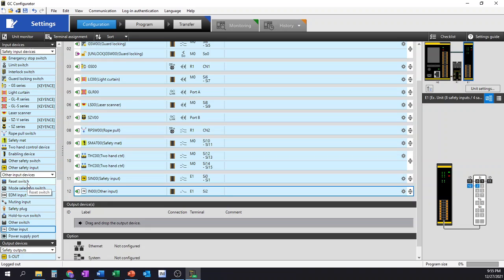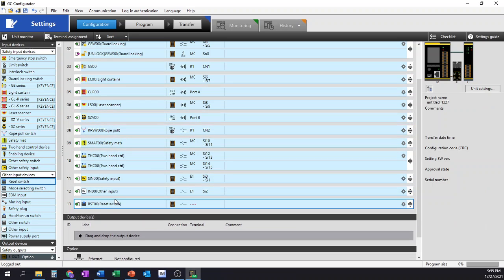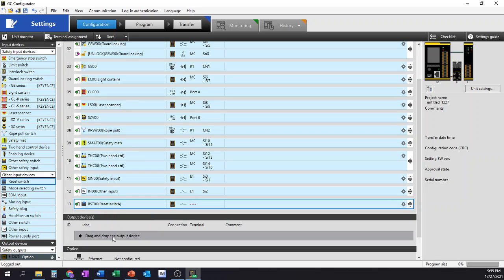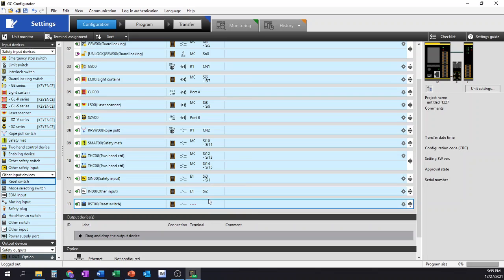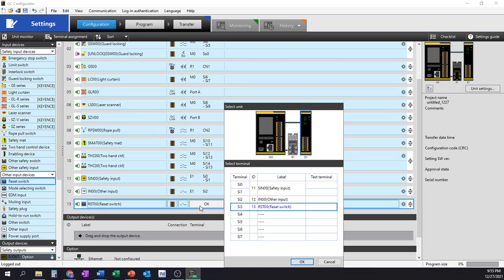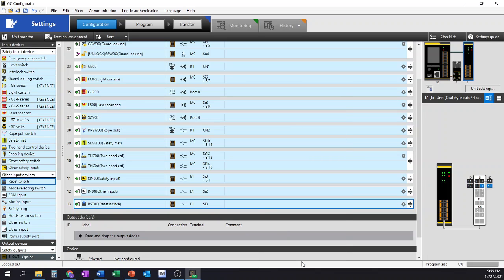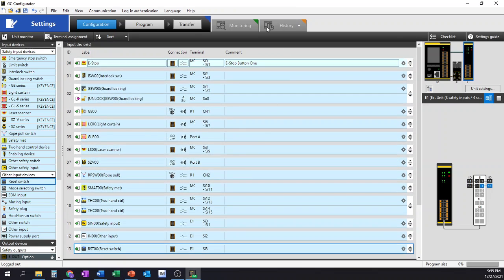Let's say we need to use a reset button. Now generally all of our circuits are going to require a manual reset rather than an automated reset. Keyence does give us the reset switch. Generally we call that like a power on or something along those lines, safety reset, something in there. And we just assign that as a single individual input to us. Again, there are other options that we do have, so we might have like a muting input, or an EDM input, or a safety plug. Those are options that Keyence does offer us for our particular programming, but for a majority of our programs, a majority of the programs in the field that you'll see, this pretty much covers all of your inputs that you're going to have. In fact, this probably covers 90% of all inputs that are in existence on most machines out there. Yes, you'll have some enabling devices, and they will have a way of how they're played into the controller, but this does cover, like I said, about 90% of your features.